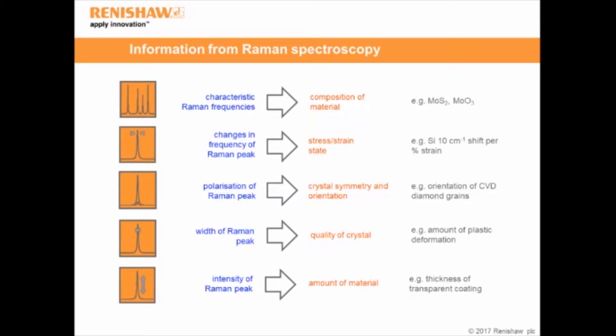The width of the Raman peak is a good indicator of quality of crystal or sample uniformity. In an ideal world, all the molecules or atoms would have equal spacing, and as a result the Raman band would be infinitely sharp. In reality, we do our measurements at room temperature, so there's some broadening as a result of the Boltzmann distribution that the material sees, and this gives us a finite width. But if we start to add defects to our material, or expose it to different stresses and strains, we'll see this peak broaden, and we can use this to gauge the amount of plastic deformation in the material.